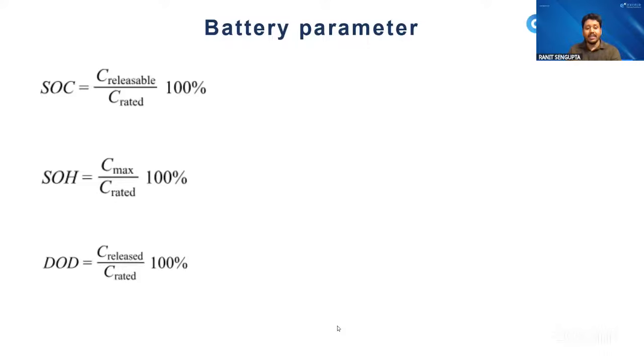Most of the time, if our SOC capacity is 100 ampere hour, we set 90 ampere hour as the DOD limit -- meaning up to 90 ampere hour should be discharged, and 10 ampere hour should be reserved for emergency applications. That is the difference between SOC and DOD.